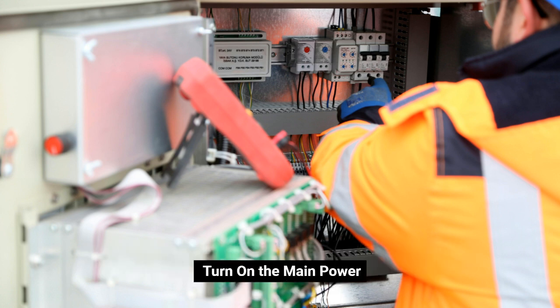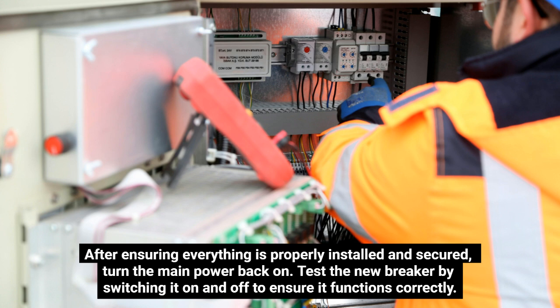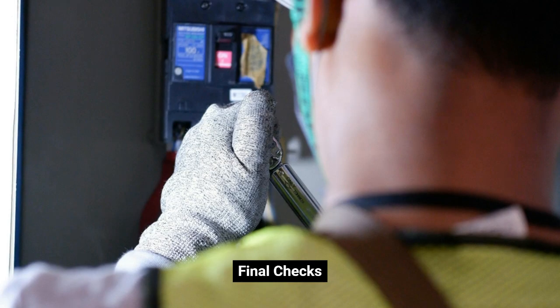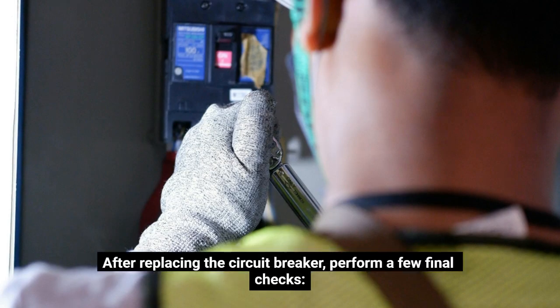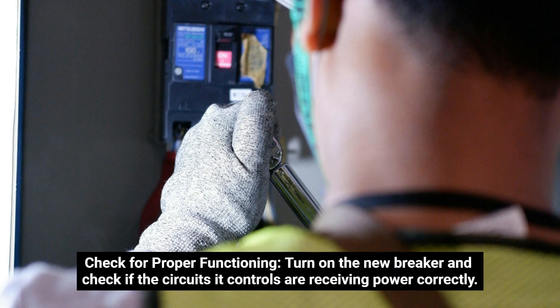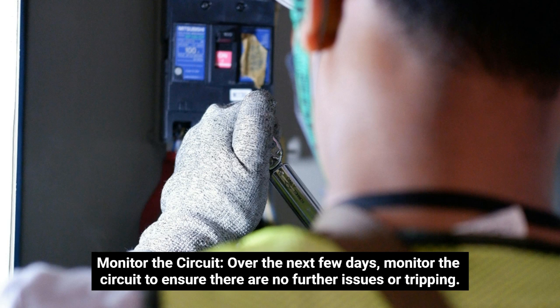Turn on the main power. After ensuring everything is properly installed and secured, turn the main power back on. Test the new breaker by switching it on and off to ensure it functions correctly. Final checks. After replacing the circuit breaker, perform a few final checks. Check for proper functioning. Turn on the new breaker and check if the circuits it controls are receiving power correctly. Monitor the circuit. Over the next few days, monitor the circuit to ensure there are no further issues or tripping.